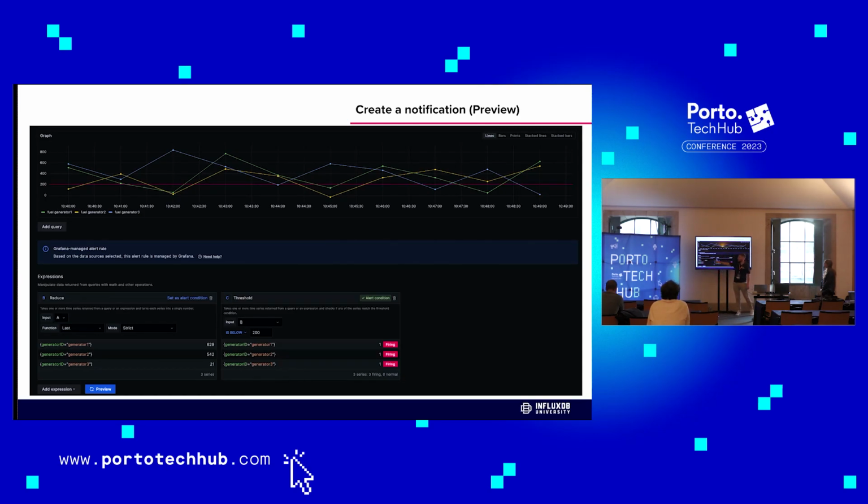We're then passing our results from B into C, and we're basically going to say if any of these generators fall below 200, then we want our result to fire. We basically want that check to become an emergency, that our fuel levels have dropped lower. So let's start off by doing that now.